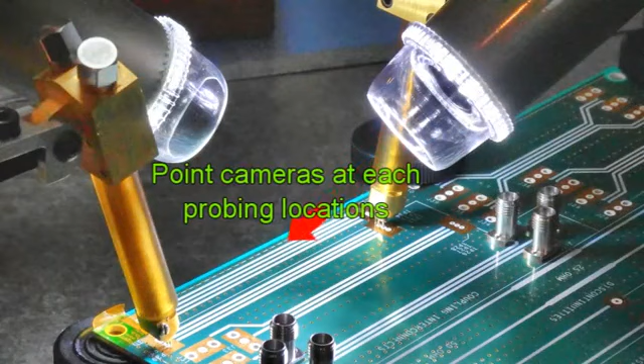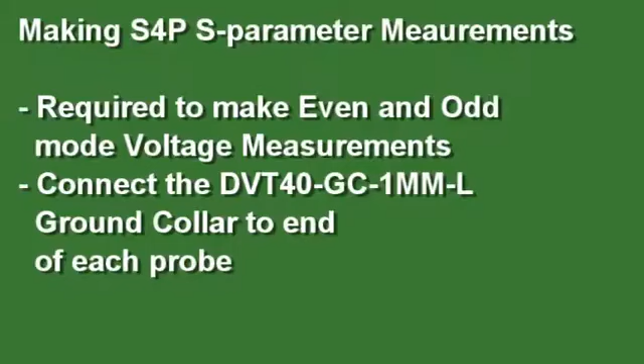Next, we're going to focus the camera on each probing location. Point each camera in the direction of each of the probes that are making contact with the test pads. Insert each camera USB connector to the PC, run the software, and create a window for each camera display. To focus the image, use the thumb controls on the side of the camera and the controls on the FP100.